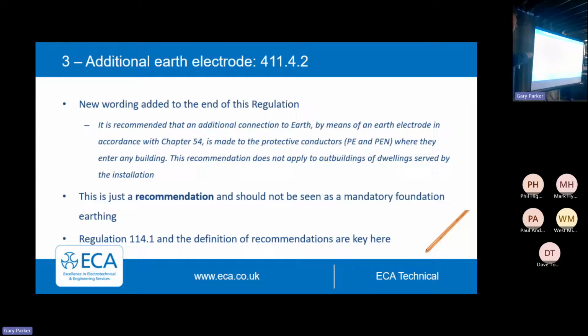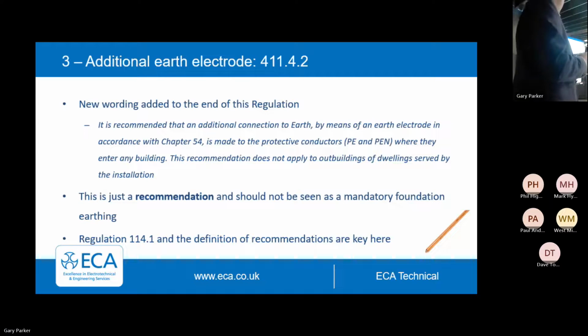Put this one in, because it's caused a lot of problems in 2 ways. About 5 years ago, somebody decided that we should put an additional earth electrode on all TN earthing systems, or that it was a good idea to do that. It wasn't a good idea. It wasn't feasible, it wasn't practical. So it has been changed from being mandatory to a recommendation.